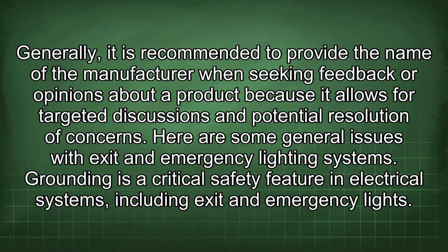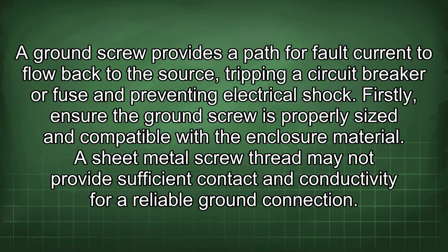Here are some general issues with exit and emergency lighting systems. Grounding is a critical safety feature in electrical systems, including exit and emergency lights. A ground screw provides a path for fault current to flow back to the source, tripping a circuit breaker or fuse and preventing electrical shock.